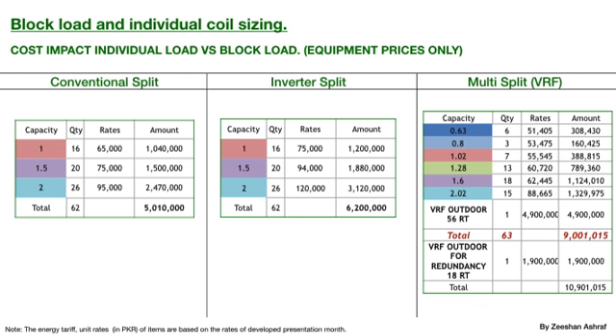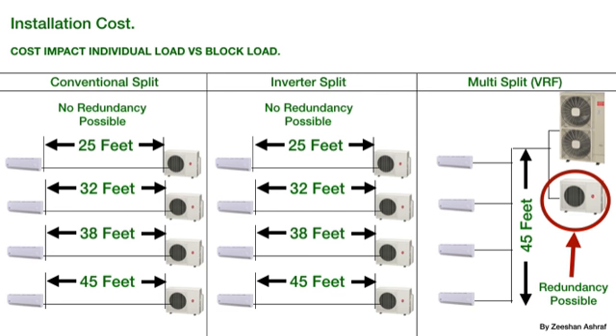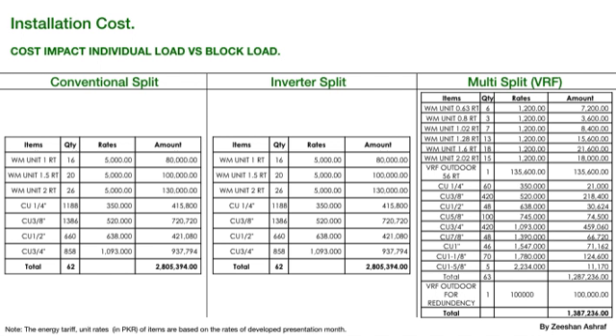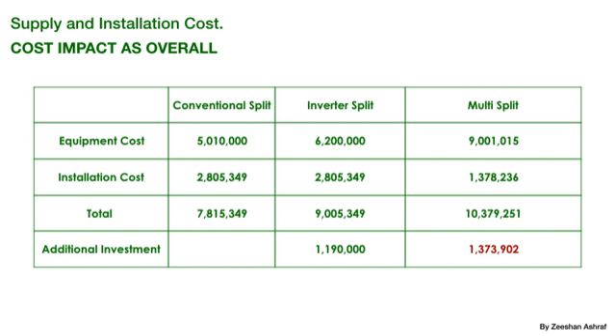As per our case study for the same complex, the equipment cost for each option is as mentioned. Conventional split costs 5 million, inverter split 6.2 million and VRF 9 million. As you can notice, for every indoor unit there is a separate couple of pipes going from the indoor to the outdoor unit, but in the case of VRF you have a single pipe connected to the outdoor unit. You can notice the installation cost of single AC systems is almost double that of the multi-split, based on the same installation rates. The extra investment is negligible.